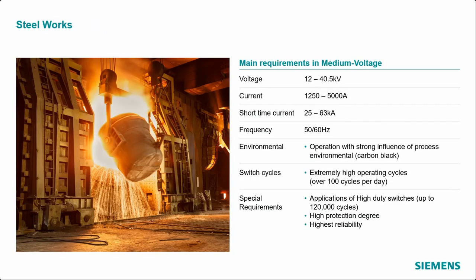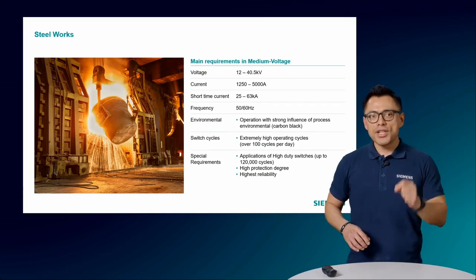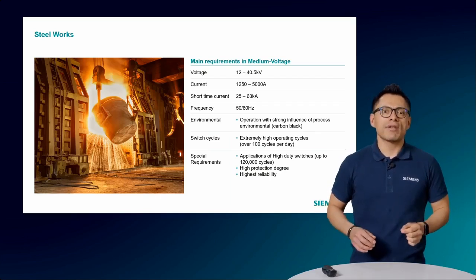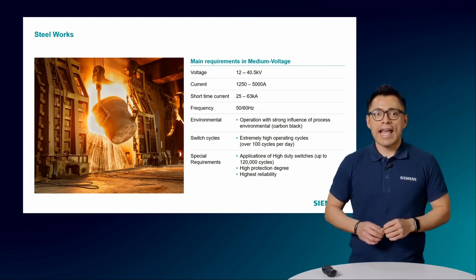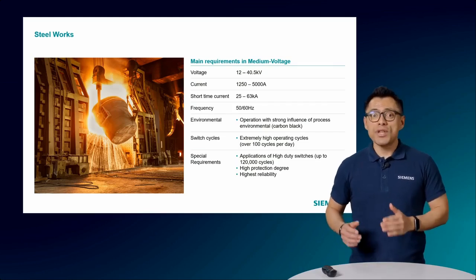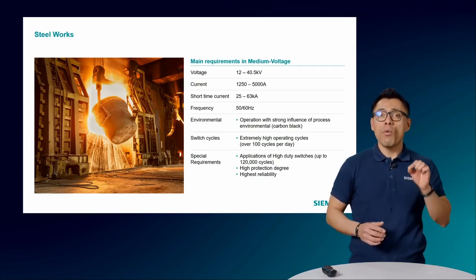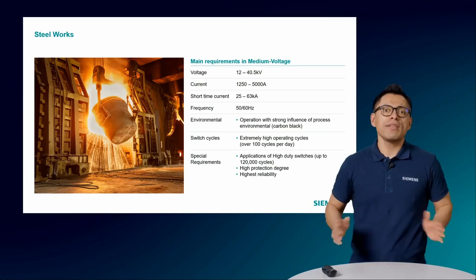There are some other applications with high demanding requirements, like the steel industry. Due to the high power demand and heavy machinery, in this application, medium voltage switchgear needs to have a high voltage and current capacities and extremely high operating cycles. They also need to have a high durability design to operate in the harsh conditions of steel plants. Just to give you an idea, a switchgear in many common applications may switch around 1 time per year, maximum 2, and only for inspection purposes, while a switchgear in the steel industry can switch over 100 times per day. This is an incredible performance requirement.